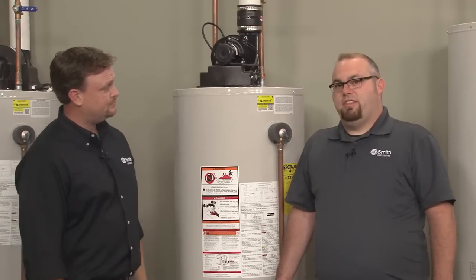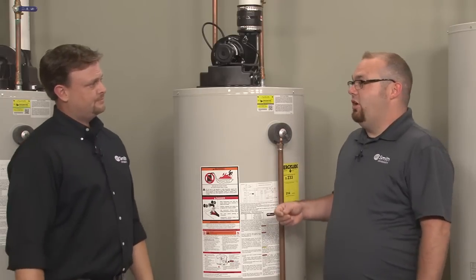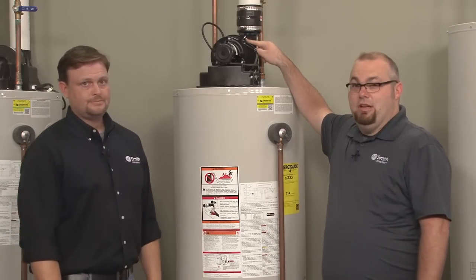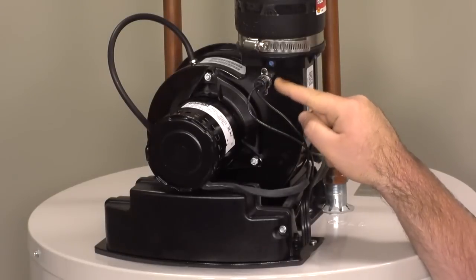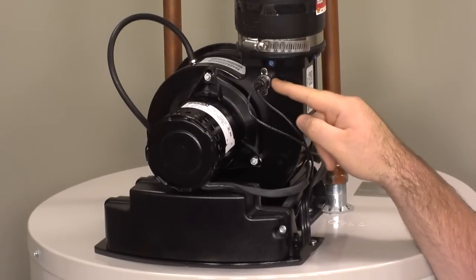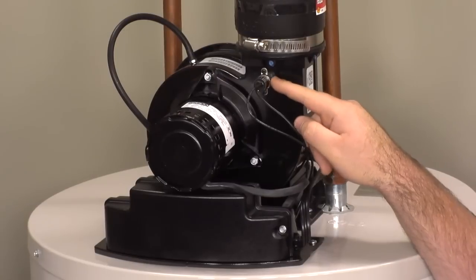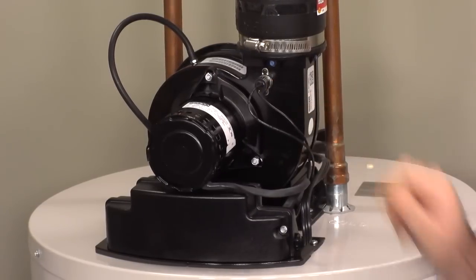And there's a couple other things to keep in mind. You also have to always remember that your vent temperature limit switch or high limit switch is on that circuit too and can be responsible for that. So you always want to make sure the switch is closed, meaning that it has continuity or the contacts in it are closed.